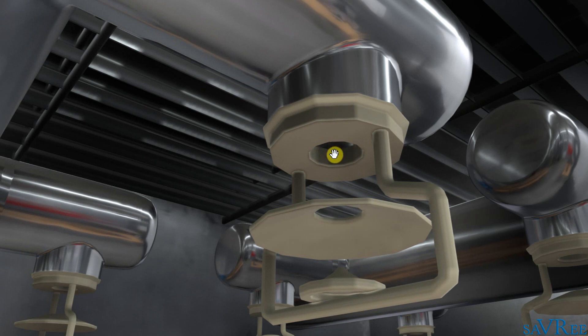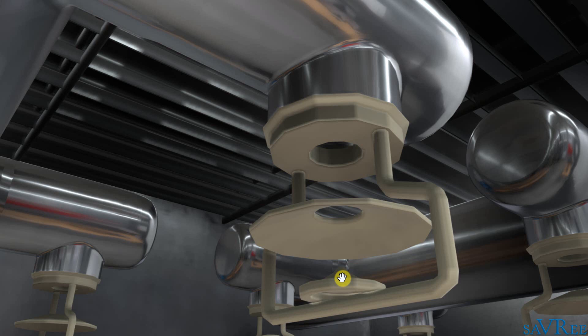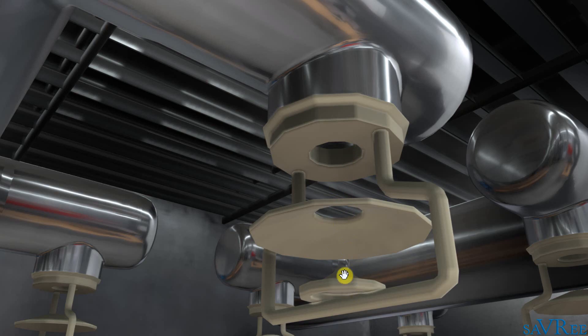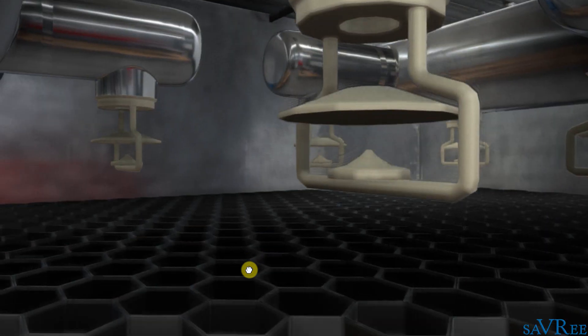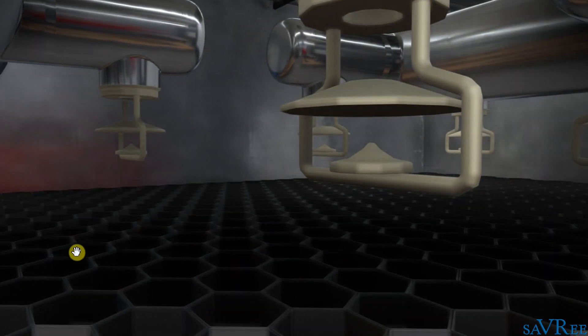And then it's going to impinge upon this plate here and the one below it. And we're going to end up with a circular spray pattern. So that's what these two plates are doing, allowing us to spray the water over a large area and spray the water out evenly. So we're not getting just a huge jet of water coming out the center here and then landing on this item here, which is the fill.